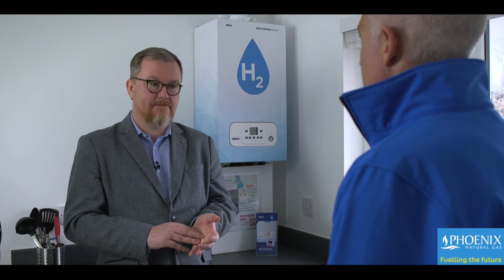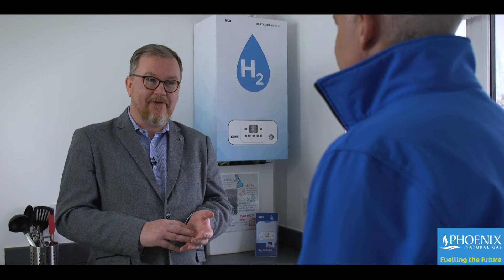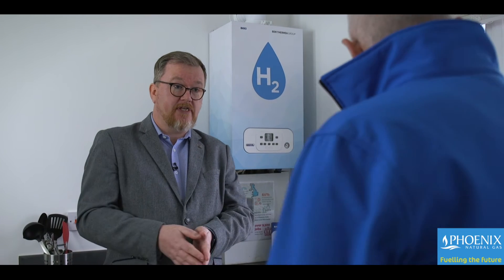So to be clear: this boiler is 100% hydrogen. The hope is to get hydrogen-ready boilers into householders in the near future to operate off blended hydrogen, which can then be upgraded to full hydrogen. What are the timescales? We're waiting for a consultation from the Department for Business, Energy and Industrial Strategy, which will talk to a potential mandate for hydrogen-ready boilers — it's looking likely that 2026 could be a regulatory line in the sand where all boiler sales must be hydrogen-ready. As a business we're committed to 2025, so all of our products sold in the UK will be compatible with low-carbon fuel — either electricity or hydrogen-ready.